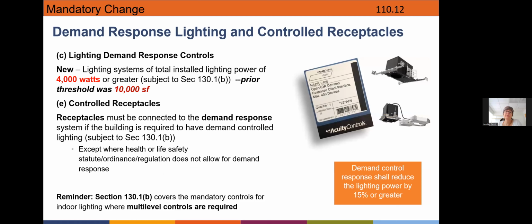With demand response lighting and controlled receptacles, on the surface it doesn't seem like too much has changed, but if you dig into it a little more, there's now a change where it says lighting systems with total installed lighting power of 4,000 watts or greater will be subject to these requirements. Previously, it was stated that a project with 10,000 square feet or more would be subject to it. So they've taken it away from looking at how big the building is to actually how many watts are being installed. And that 4,000 watts is going to have an impact. It's predicted that it will help bring down energy use by about 15%.